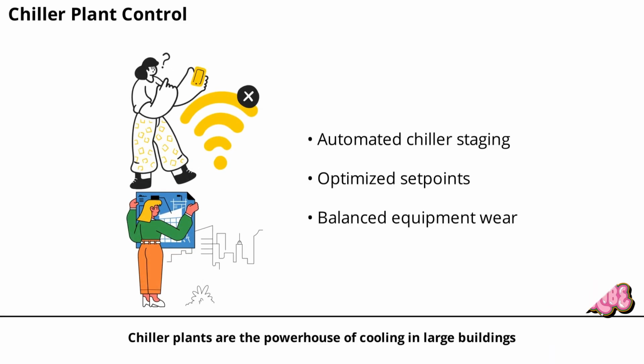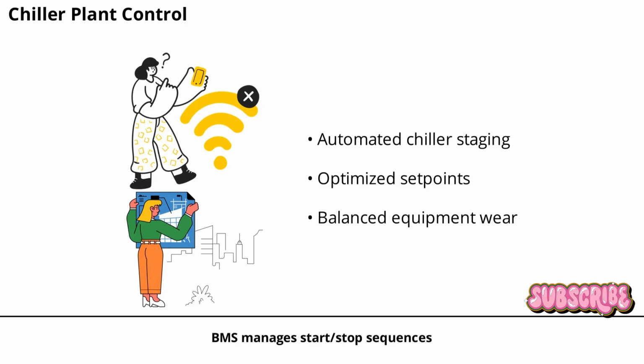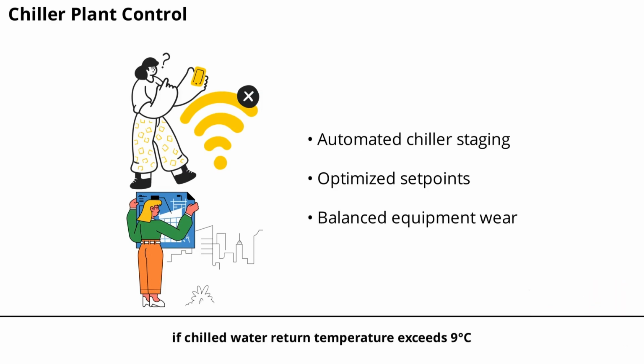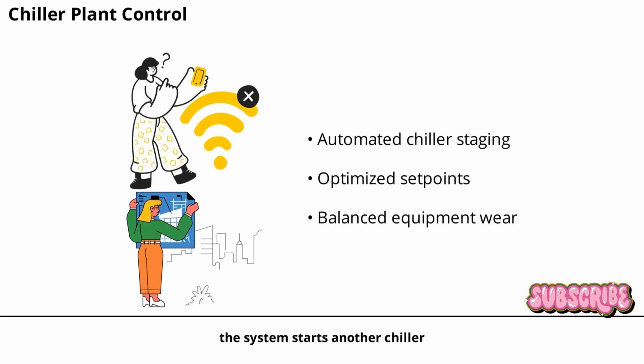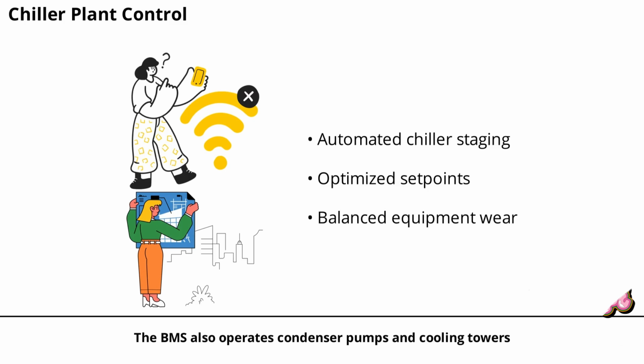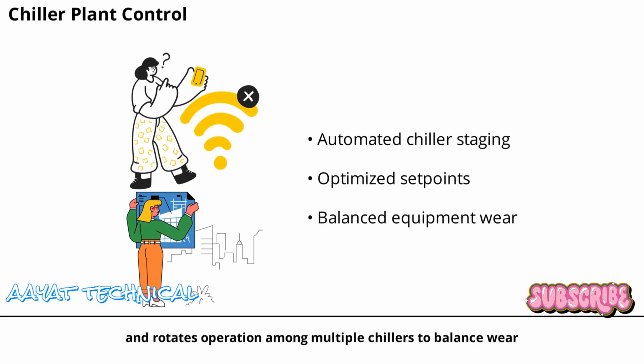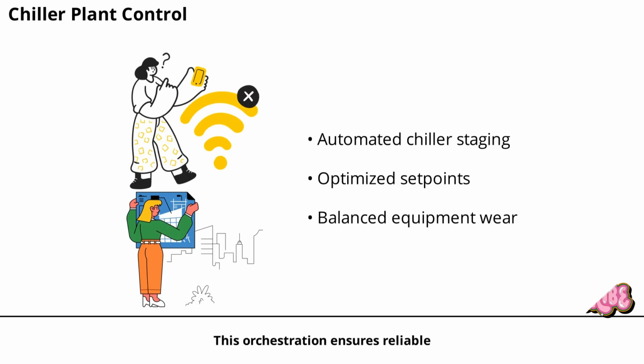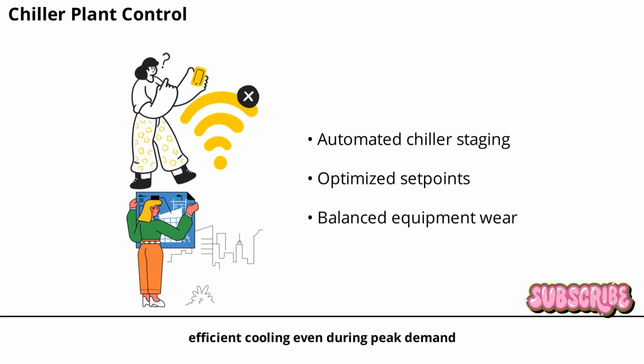Chiller plants are the powerhouse of cooling in large buildings. BMS manages start, stop sequences, load staging, and set point optimization. For example, if chilled water return temperature exceeds 9 degrees C, the system starts another chiller. If it drops below 6 degrees C, it stops one. The BMS also operates condenser pumps and cooling towers and rotates operation among multiple chillers to balance wear. This orchestration ensures reliable, efficient cooling even during peak demand.